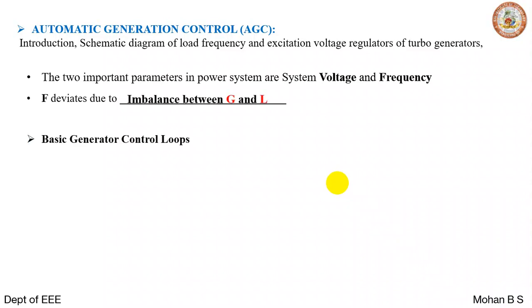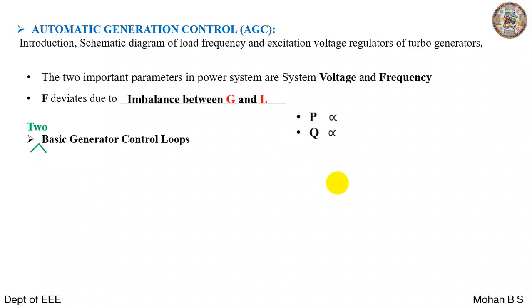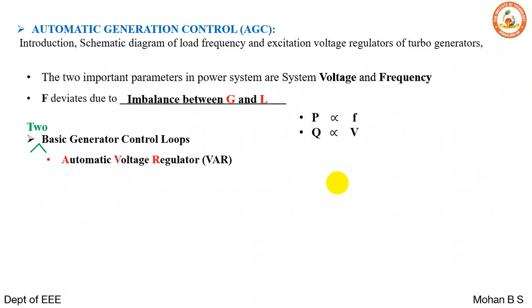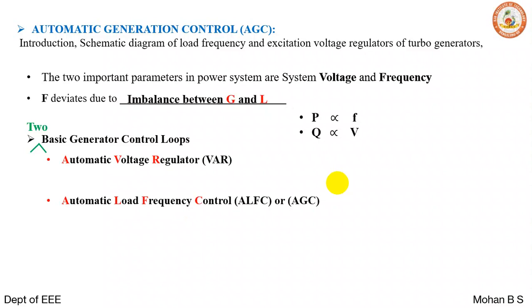We have two basic generator control loops. P is actually proportional to F, and Q is actually proportional to V. So the two loops are the automatic voltage regulator and the automatic load frequency control, which is also known as automatic generation control.